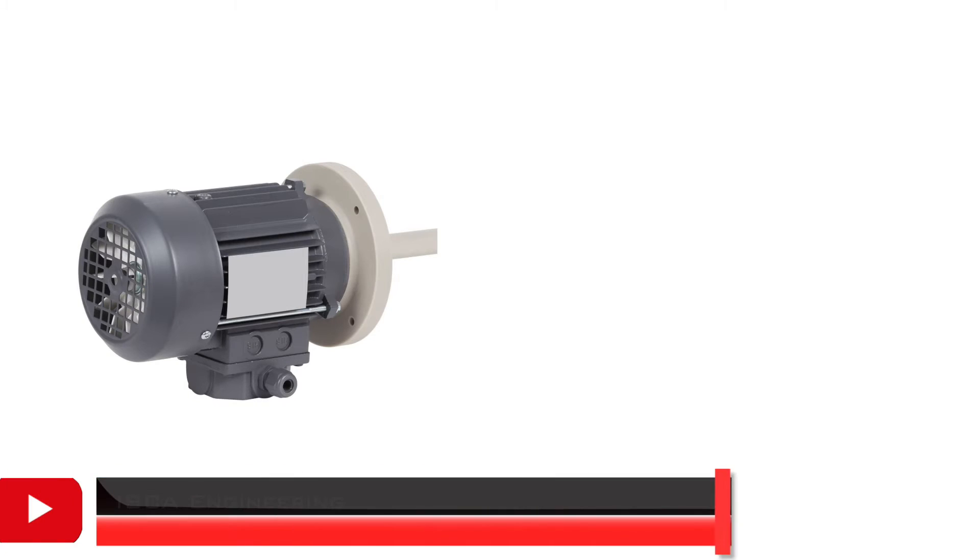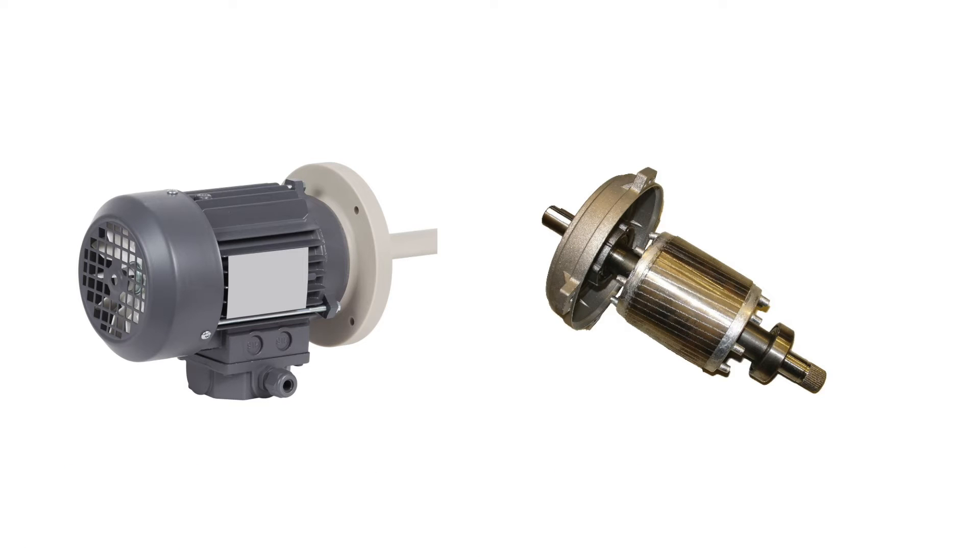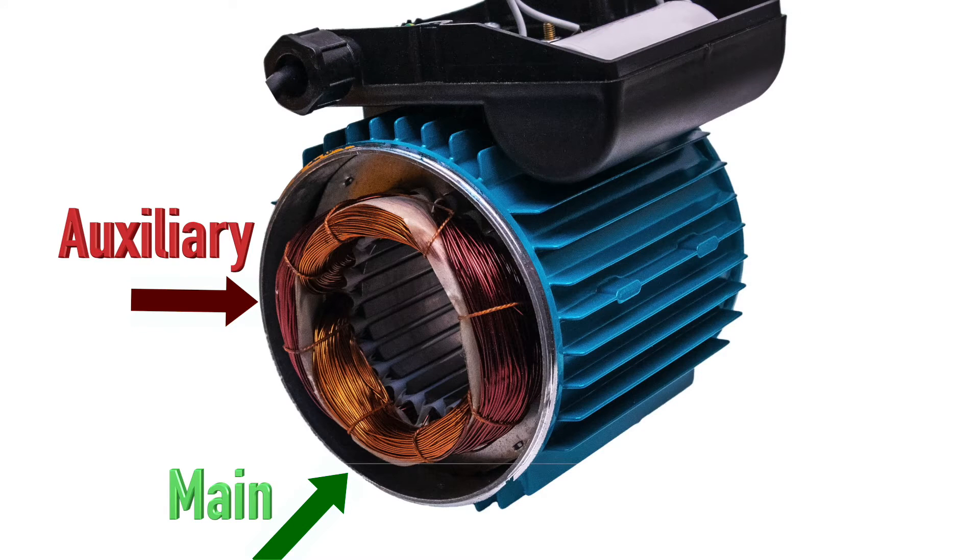The split phase motor uses a squirrel cage rotor that is identical to that in a 3 phase motor. They consist of two windings, one being the main winding, and the other one being the auxiliary start winding, which is displaced in the stator 90 mechanical degrees from the main winding.